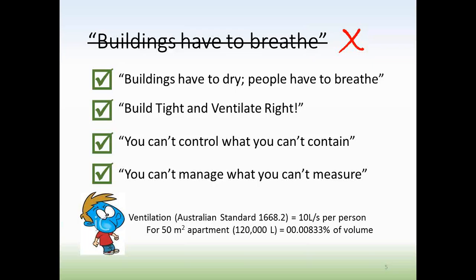Just for illustration purposes, a 50 square meter apartment contains 120,000 liters of air, and the Australian standard for ventilation calls for 10 liters per second per person. That's every second. That's 0.008% of the apartment volume. It's an incredibly small amount of air that you actually need to meet indoor air quality.